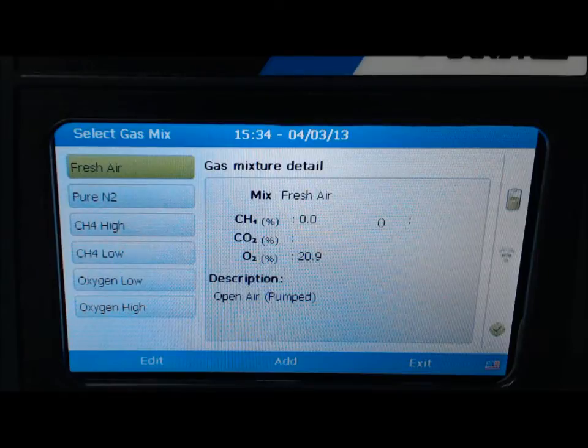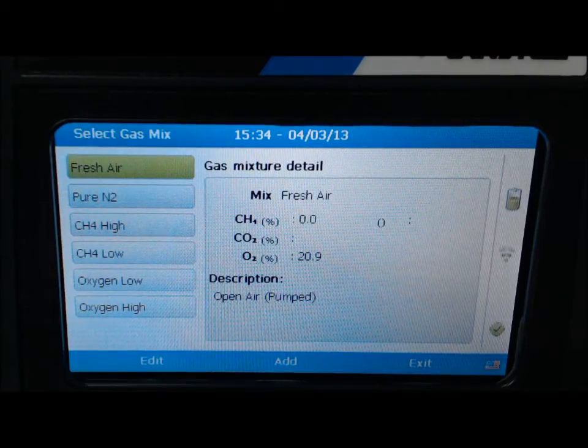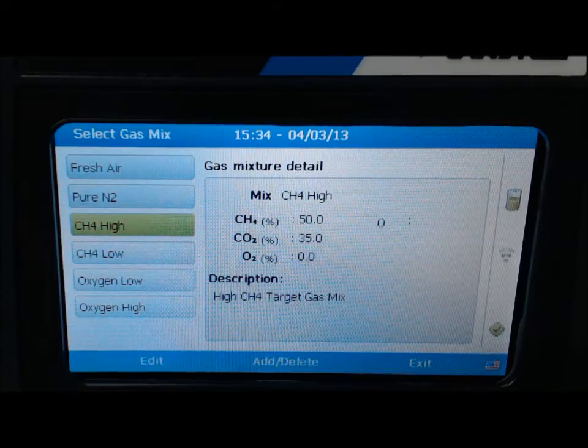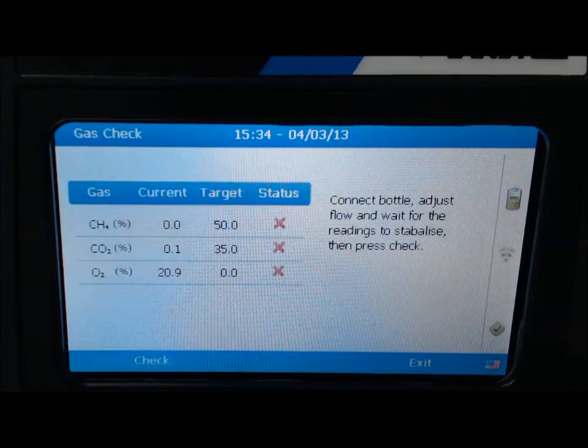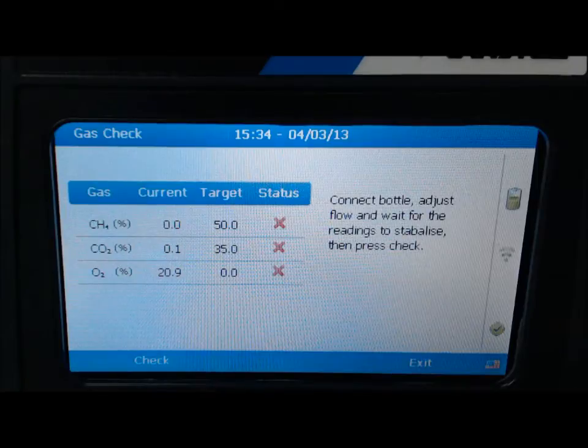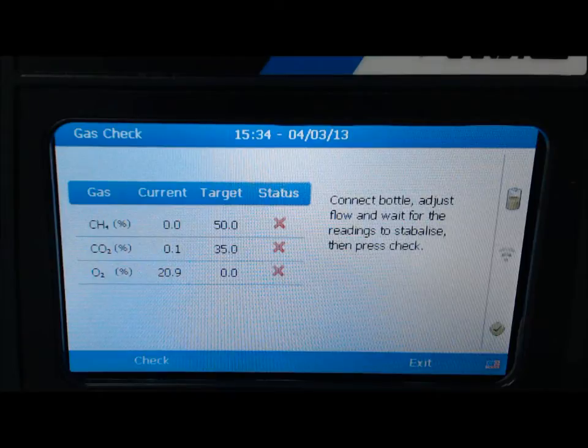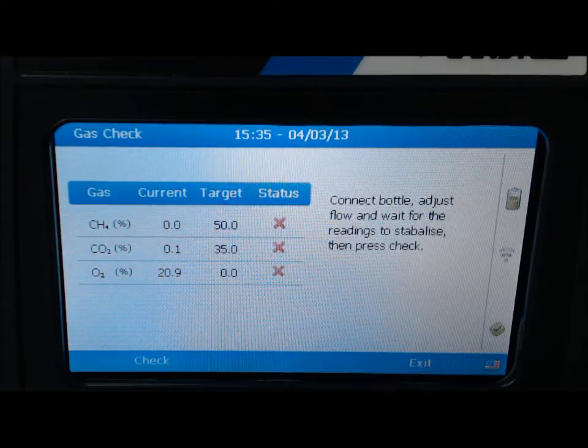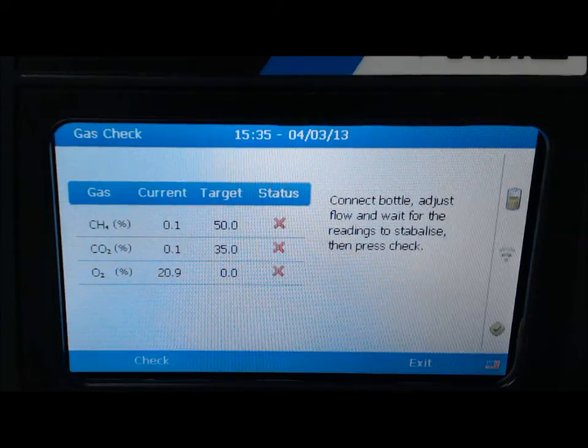Scroll down using the arrow keys and select CH4 high to span the CH4 and CO2, then press enter. Notice the gas mixtures have been predetermined to 50% CH4 and 35% CO2. At this point, connect the 50% CH4, 35% CO2 calibration gas mix to the inlet, which is the white colored port on the analyzer. Open the pressure regulator for gas to start flowing and select check when readings have stabilized.